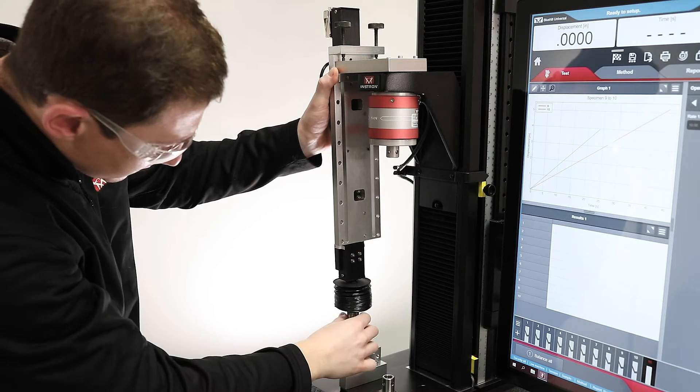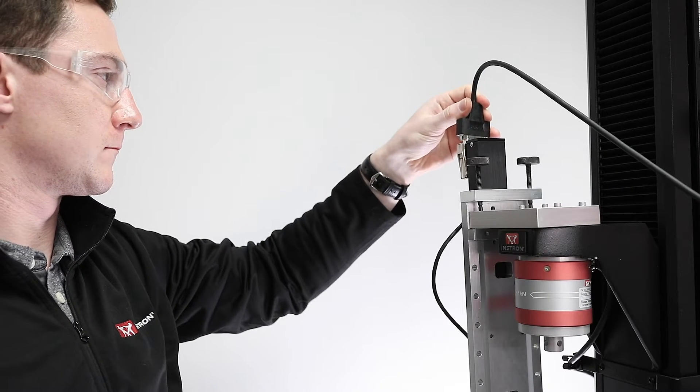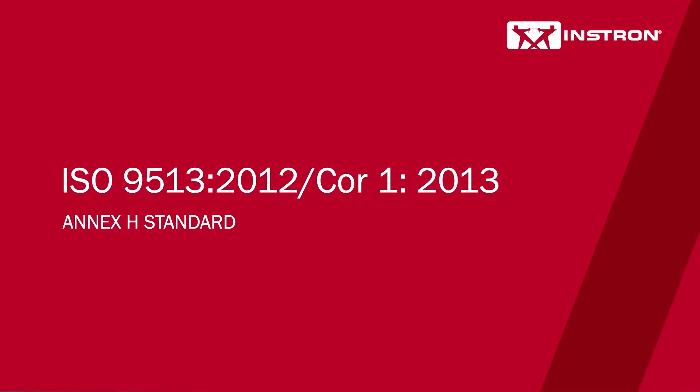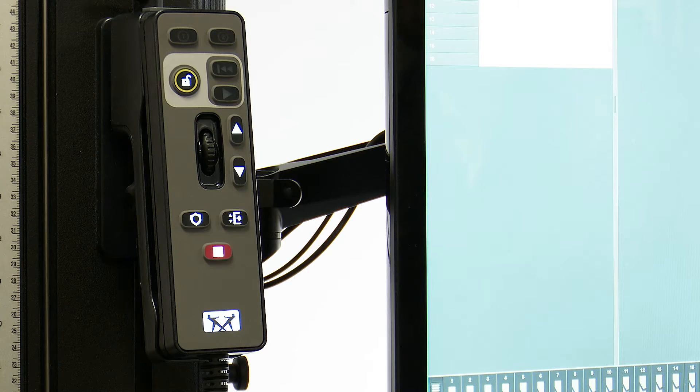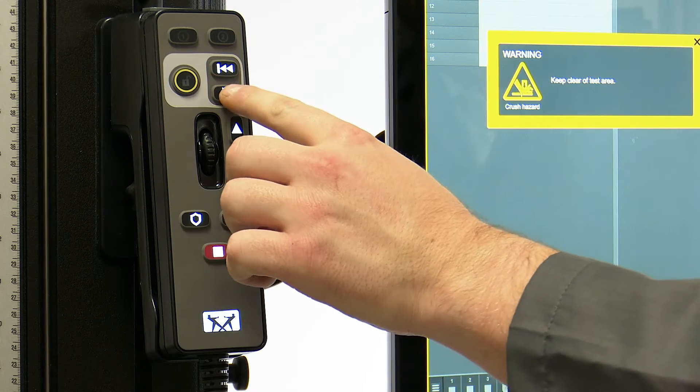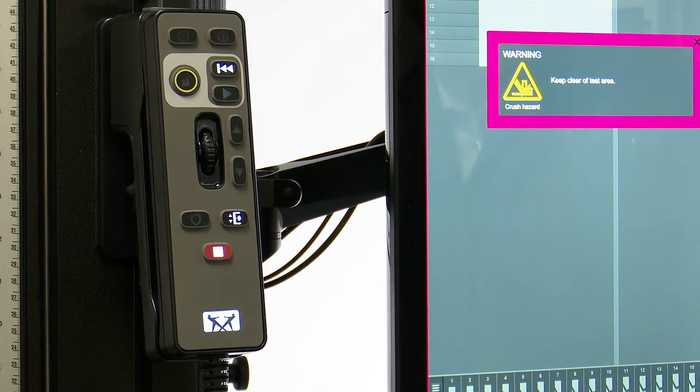For displacement verification we can verify to ASTM E2309 or ISO 9513 2012-Core 1-2013 Annex H standards, and for speed verification we can verify to ASTM E2658 standard.